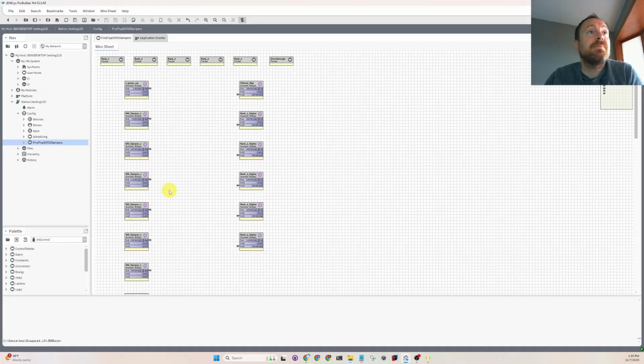So I have some generic algorithms that aren't very useful in ordinary HVAC. You wouldn't be doing this in the BAS, but it does kind of lay the framework for Guideline 36. Guideline 36 for air handling unit trim and respond is lots of counting up and down, filtering out maximum values, and it's kind of hard to do in wire sheet logic, which I'll demonstrate here. But this is just a wire sheet algorithm that I made, just with ordinary kitControl widgets.